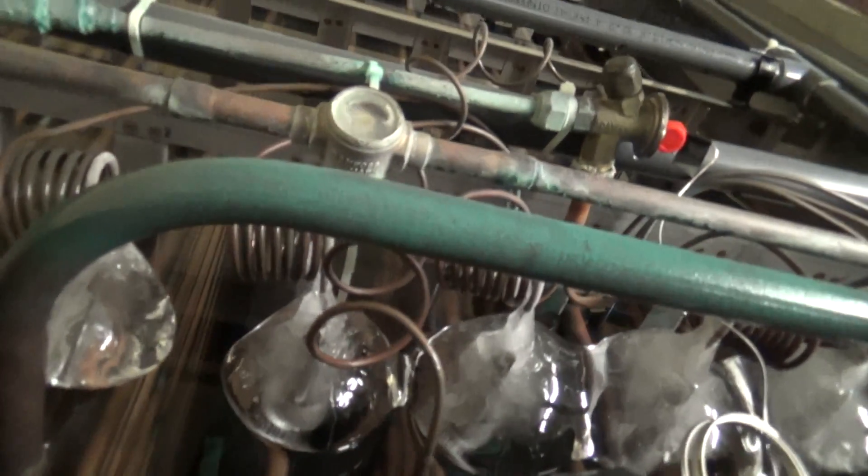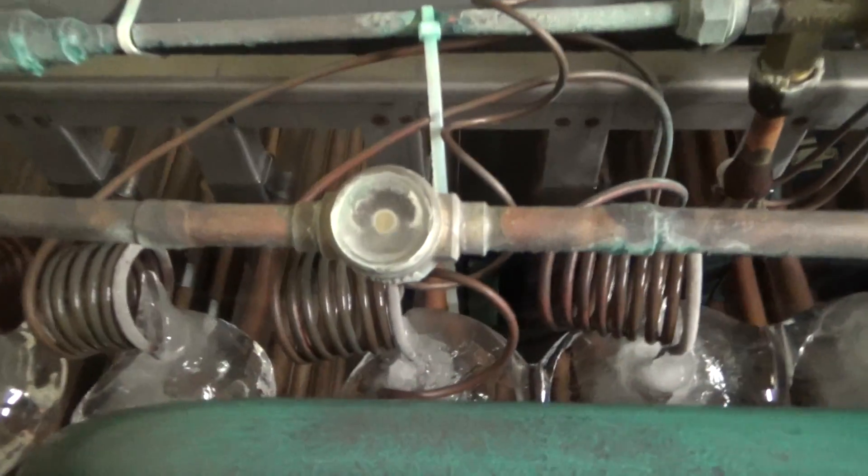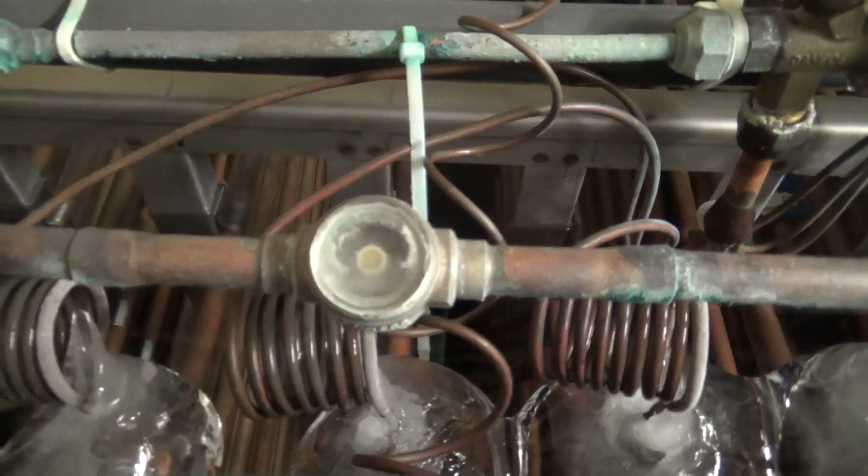Looking at this ice builder system, it's not keeping up with the volume of milk they're putting in the tank. And as you can see, that sight glass is flashing quite badly.